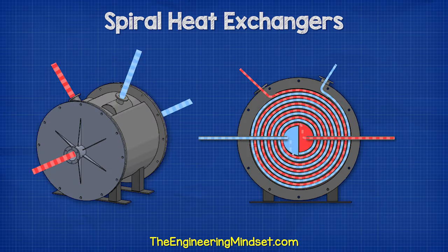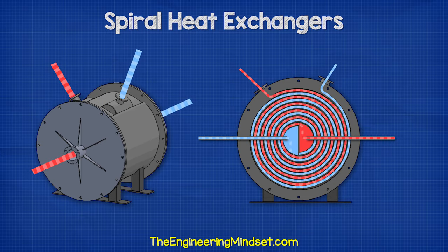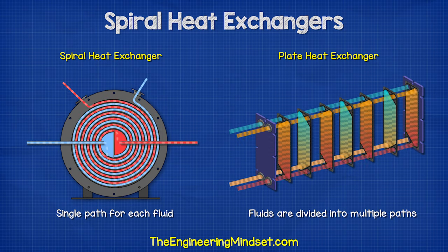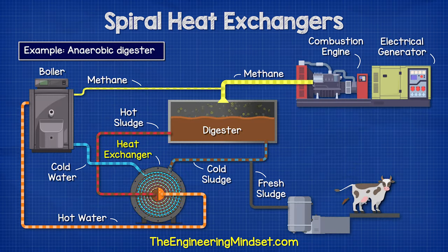The two fluids enter and exit at different temperatures. This type of heat exchanger isn't as commonly used. However, because the design has only one channel for the fluid to flow through, the velocity remains high, making it harder for fouling to occur. Whereas plate and even tube heat exchangers divide the flow into multiple paths, so these are ideal for installations where sludge-like substances are processed.